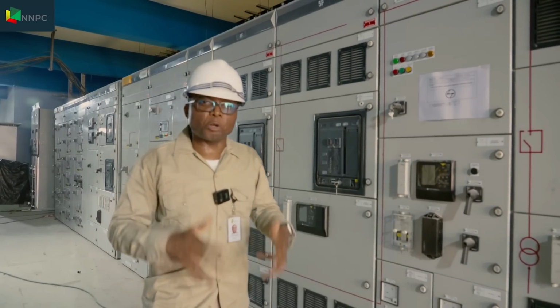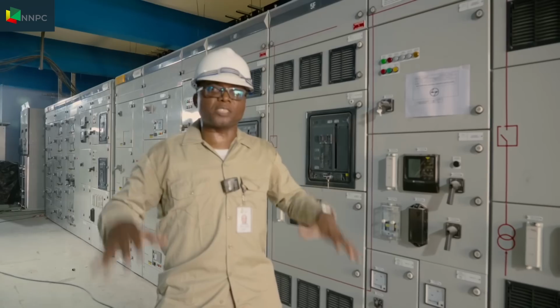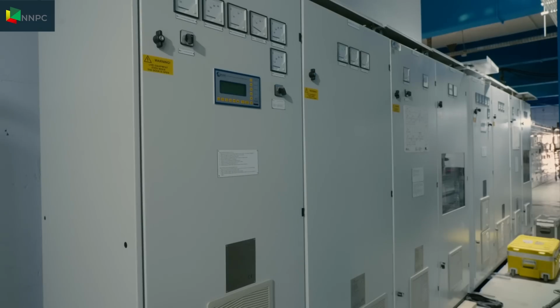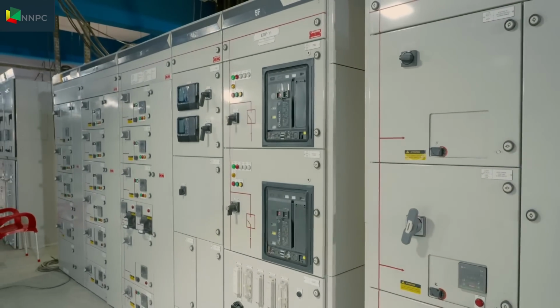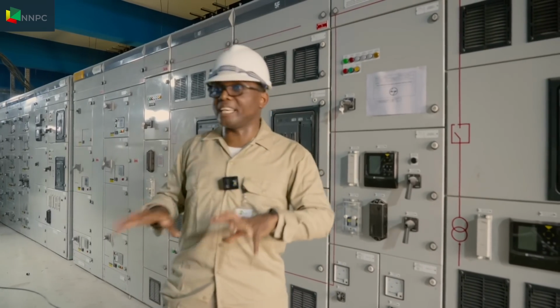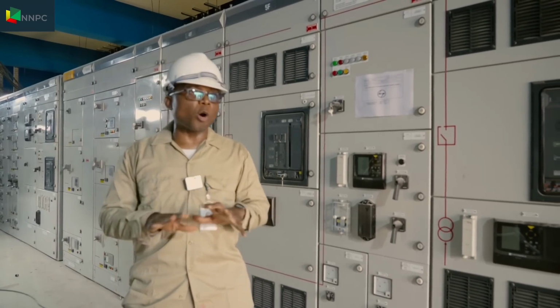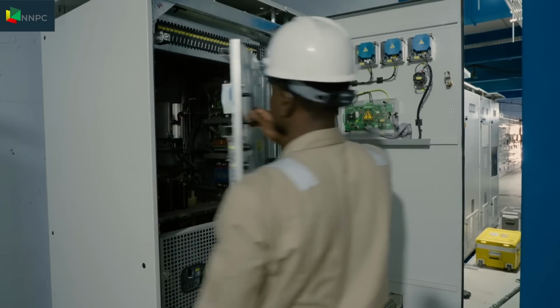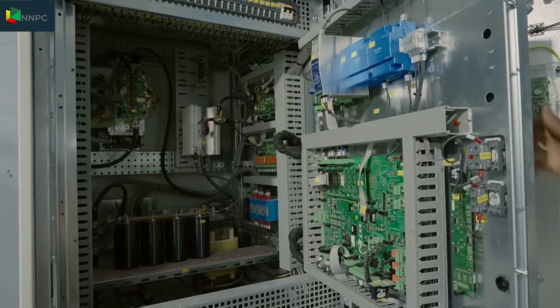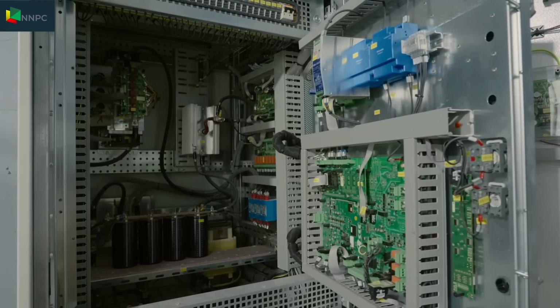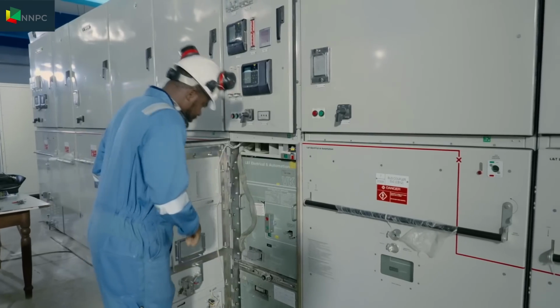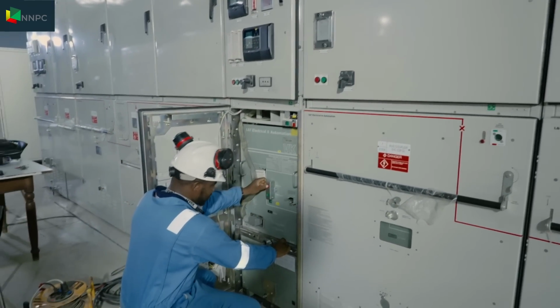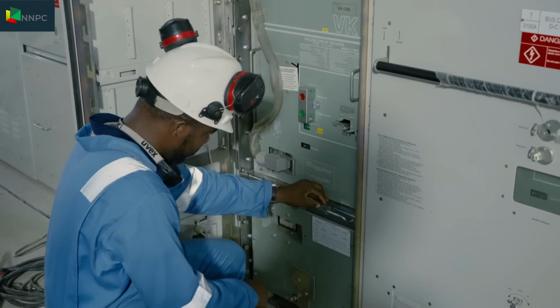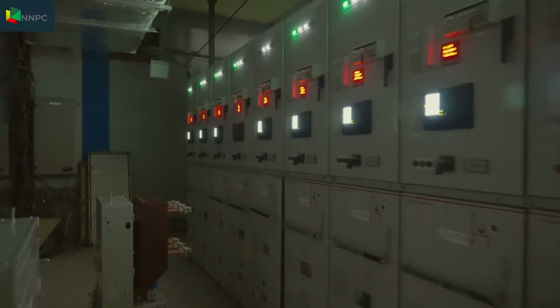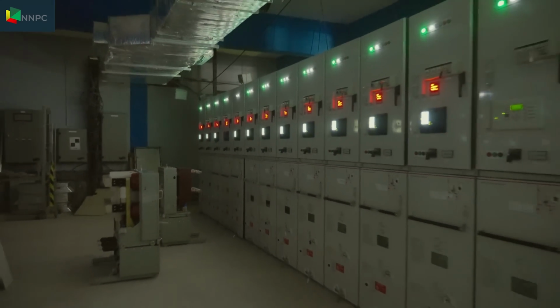During this rehabilitation project, all the equipment in this substation have been taken out. The transformers, the switchgears, the bus bars, all of them, and even the EPMS, that's the electronic power management system, has also been introduced. Everything here is brand new, latest technology, and up to date. Though brand new, a few modifications were made to improve its protection system. This was done to prevent a recurring problem in the past where a fault downstream could affect the substation. Cable termination is ongoing for other substations. Currently energized by generators, it will be powered by gas turbine generators in mid-December.